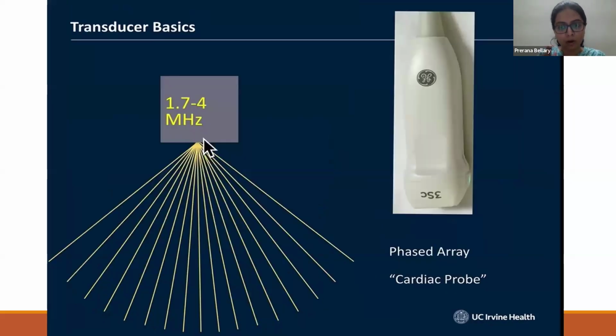Now coming to a phased array probe, this also operates at lower frequencies, 1.7 to 4 megahertz, so almost 2 to 5 megahertz. But this is called a cardiac probe. How the phased array probe is different from the other two is that the crystals are not arranged in a line or in a convex manner. They're arranged in the form of a grid containing 64 to maybe 128 crystals. And the speciality of this is that each crystal vibrates at a different time from each other, so it is used to visualize any structures in motion. So that's why it is called a cardiac probe.